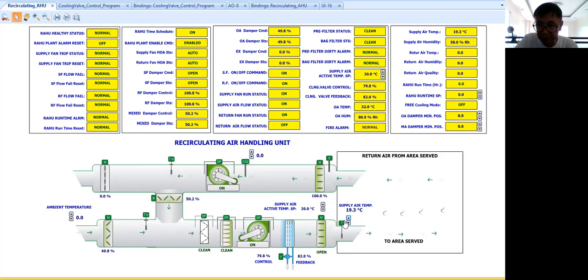So the valve will not stay in one position. It will keep on adjusting little by little, okay? So as I can see here, my valve response to the change in supply temperature is perfect. For me, it's already perfect, okay? Now let's see, 18.3, it still keeps on dropping. Now you will see the valve will try to close more, okay? So 18 degrees, so let's see, now it's 53.2, okay? So the valve responds perfectly to the disturbance in the process, okay?